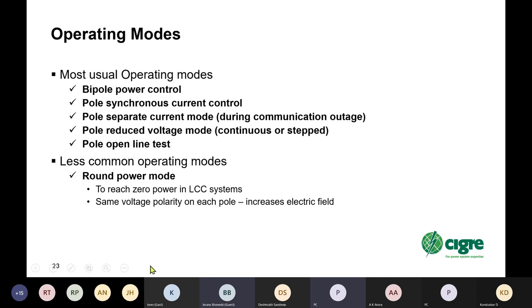So, and then also you look at operating modes, and the most usual operating modes are bipole power control, pole synchronous current control individually in each pole, pole separate power control during communication outages, pole reduced voltage mode. And reduced voltage is something that's very useful if you have polluted insulators and the wet end of the line is not up to full voltage. Frequently, by reducing the voltage to between 80 and 70%, you can continue operation and you don't have a complete outage, and the DC will withstand without further flashovers.